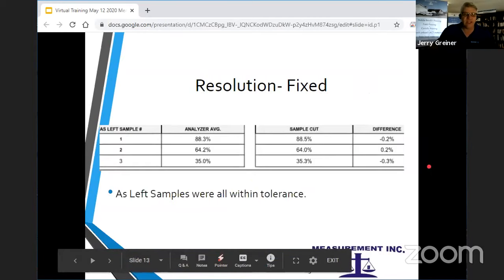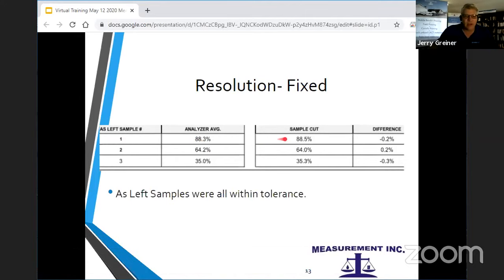To verify, we did 3 more samples, and the oil we got at 88%, 88.3 is what our analyzer read, and our sample read 88.5, a 0.2% difference. We did it a few different times, and all the samples are 0.2 or 0.3% from the reading, so it was all within their 0.5% tolerance.